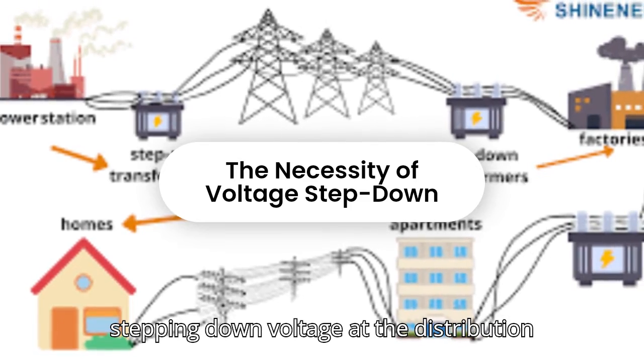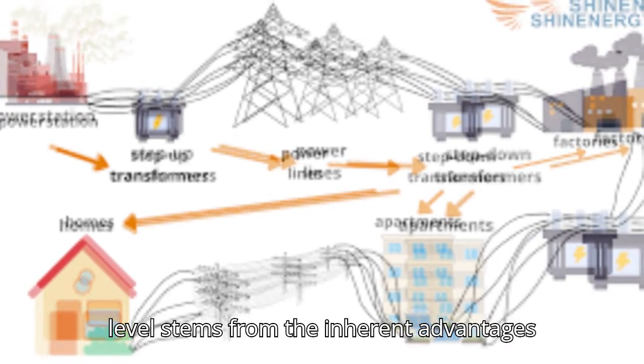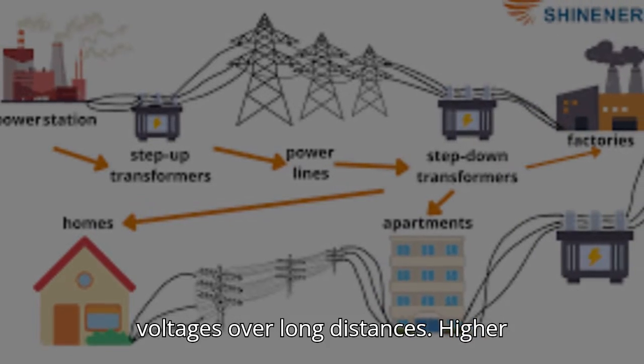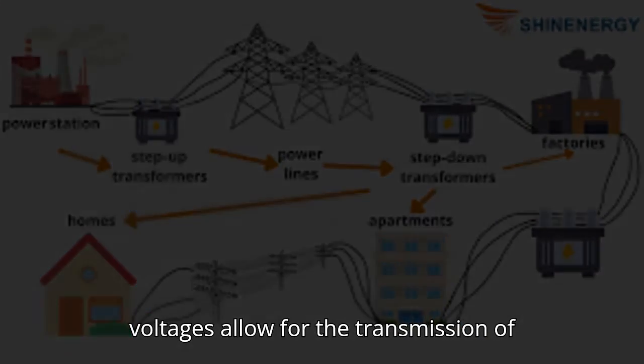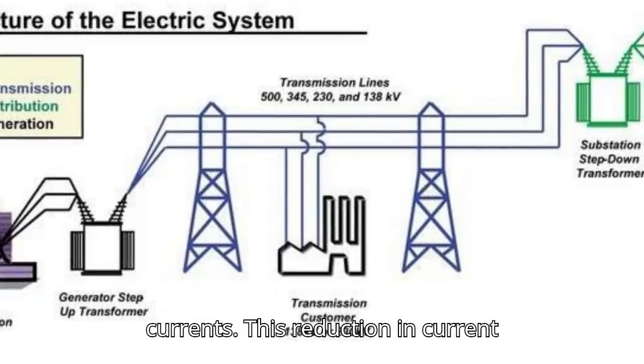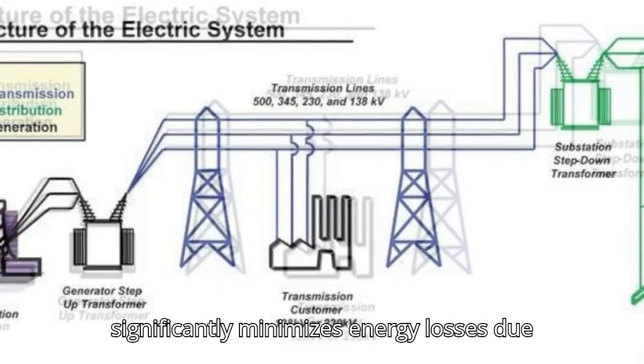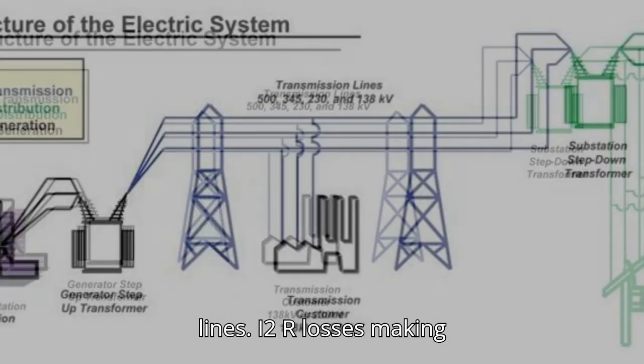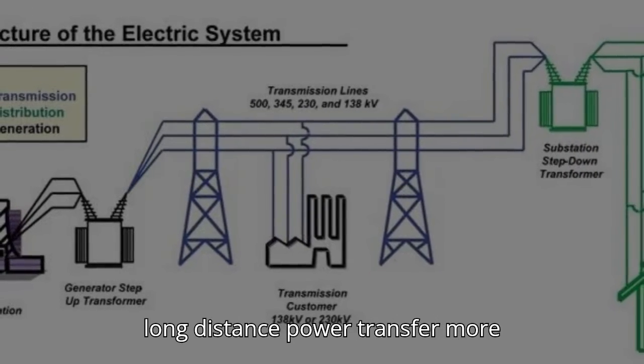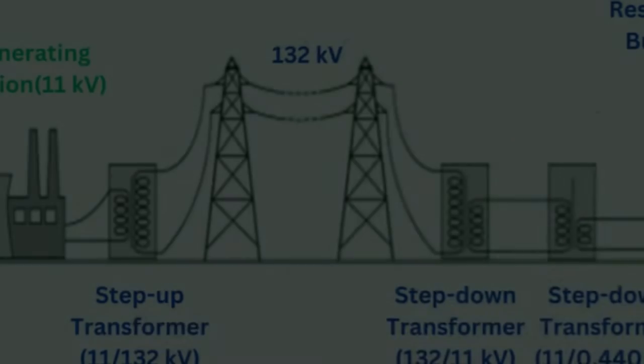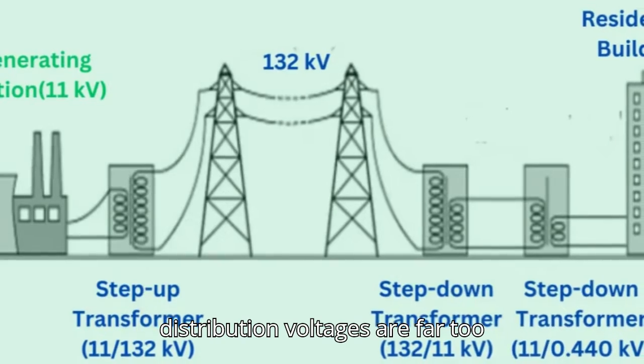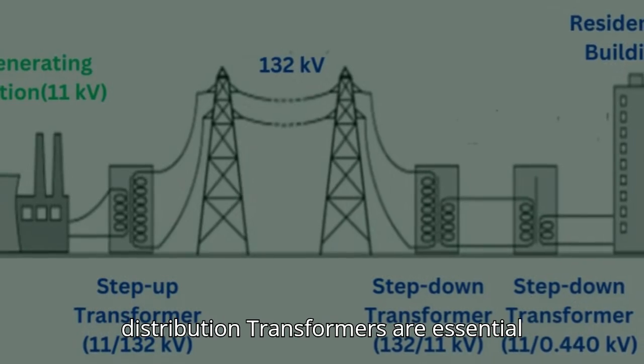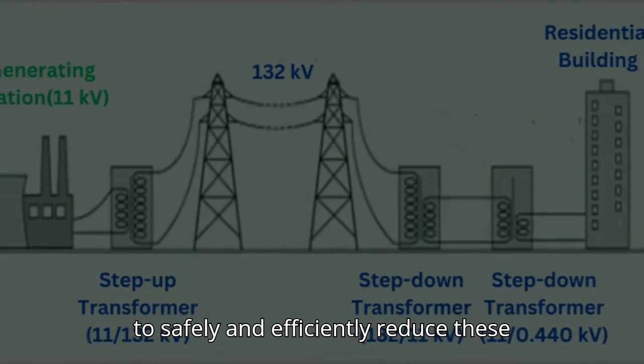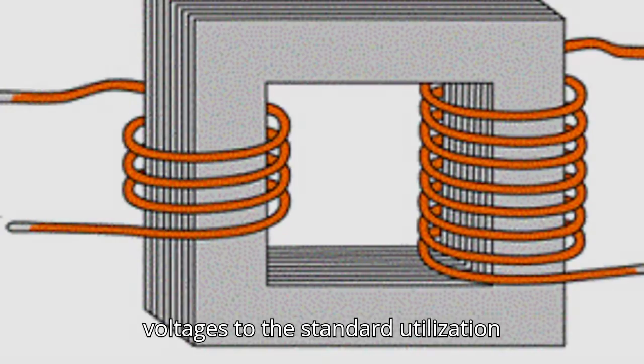The necessity of voltage step-down. The necessity for stepping down voltage at the distribution level stems from the inherent advantages of transmitting electricity at higher voltages over long distances. Higher voltages allow for the transmission of the same amount of power with lower currents. This reduction in current significantly minimizes energy losses due to the resistance of the transmission lines, I2R losses, making long-distance power transfer more efficient and cost-effective. However, these high transmission and primary distribution voltages are far too dangerous and incompatible for direct use in homes and businesses. Therefore, distribution transformers are essential to safely and efficiently reduce these voltages to the standard utilization levels required by electrical devices.